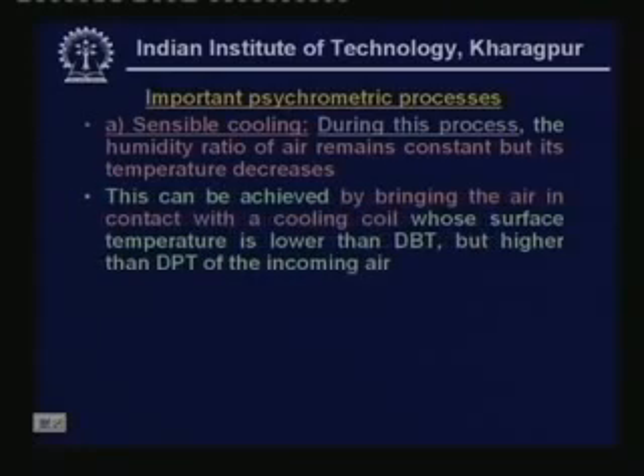This can be achieved by bringing the air in contact with a cooling coil whose surface temperature is lower than the dry bulb temperature but higher than the dew point temperature of the incoming air. Okay, because you want to achieve only sensible cooling, you do not want to add or remove moisture from the air. Okay, that means there should not be any moisture transfer. Okay, so when you are bringing the air in contact with a cold surface, for example, and if the cold surface temperature is above the dew point temperature of air, then air gets sensibly cooled. Okay, that means no moisture transfer takes place. Okay, so that is what is required if you want only sensible cooling, right.